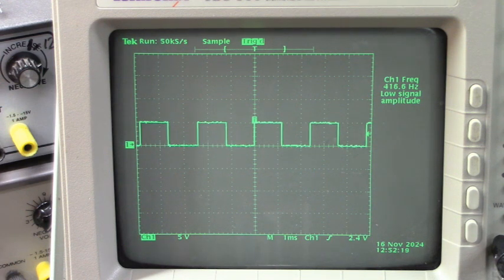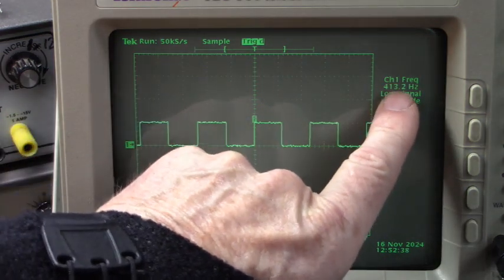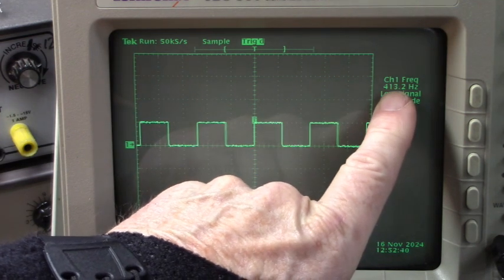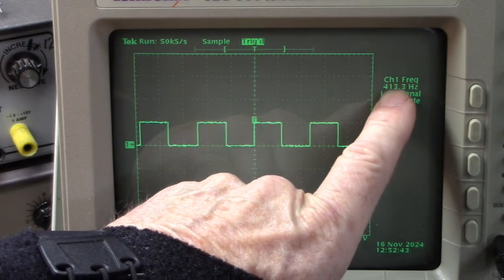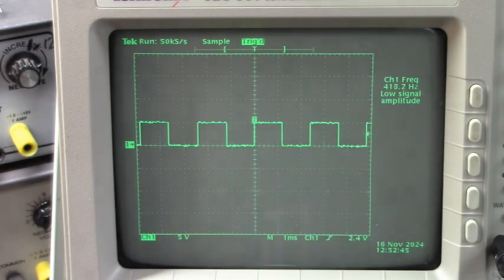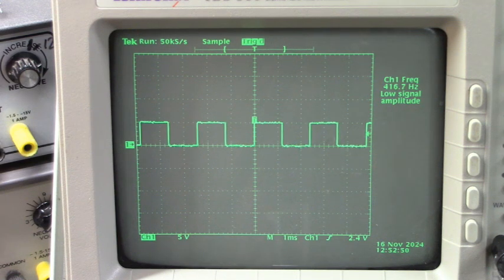Now you could even, from the frequency of that square wave, tell whether the fan was running too slow. I don't know if you can see it, but up here, where I have the frequency counter turned on, it says about 413 to 416 hertz. Now if that fan wasn't spinning at speed, that frequency would be slower.